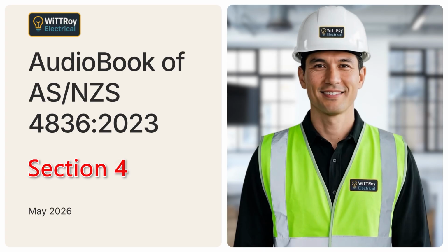A competent safety observer must be present when work is carried out on energized electrical equipment, unless the risk assessment shows there is no serious risk for the proposed work. Workers must be trained and competent in live work test procedures and in the use of test equipment. The risks include electric shock, electrocution, arc blast, and flash burn injuries. Before work starts, the risks must be assessed and documented.